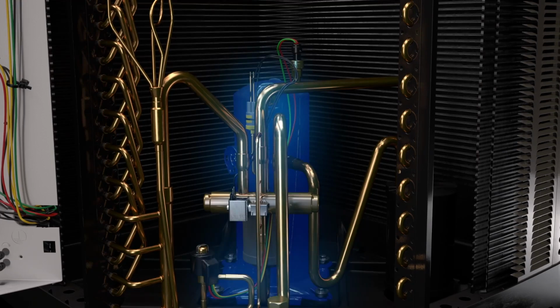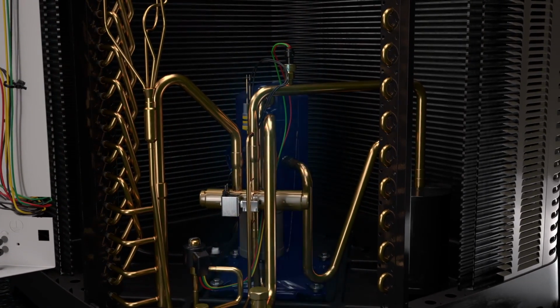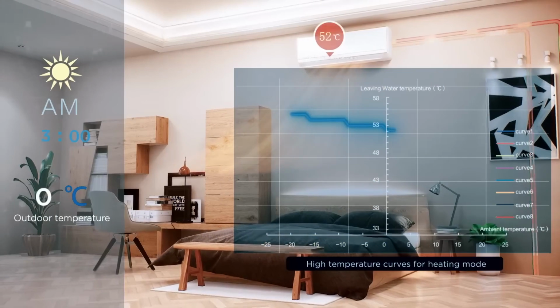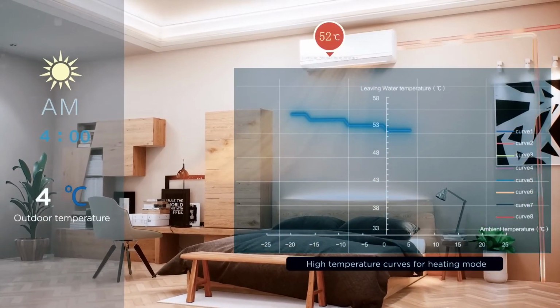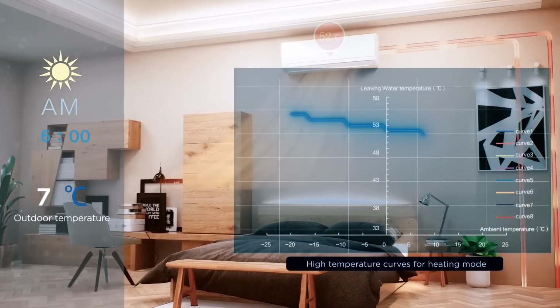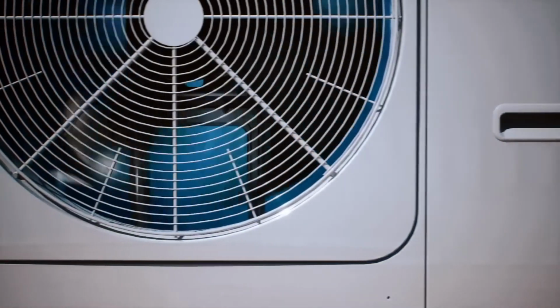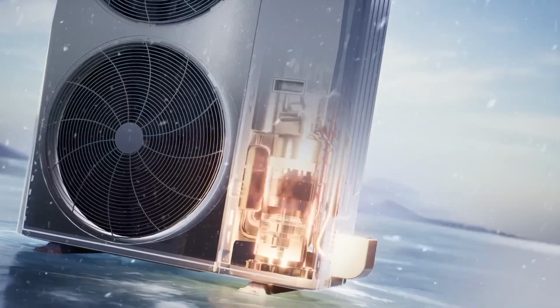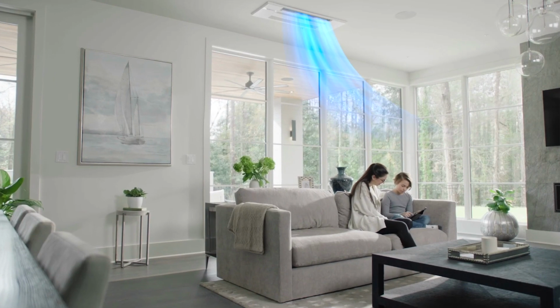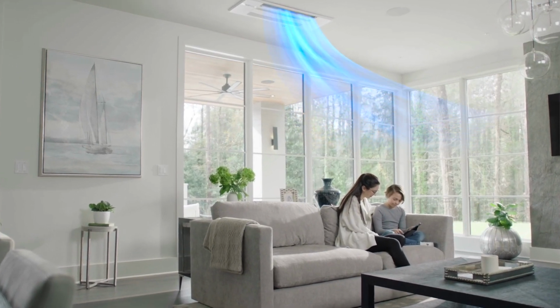Most heat pumps have variable speed motors. That is variable capacity to be precise, meaning they adjust how much heating and cooling they provide based on the temperature outside. Rather than kicking on and off constantly like fixed capacity heat pumps, variable speed heat pumps adjust their speed to the temperature difference. Variable capacity heat pumps are designed to provide optimal efficiency at varying capacities.